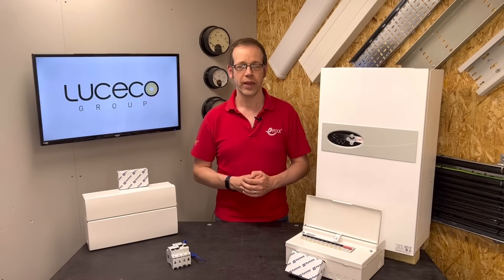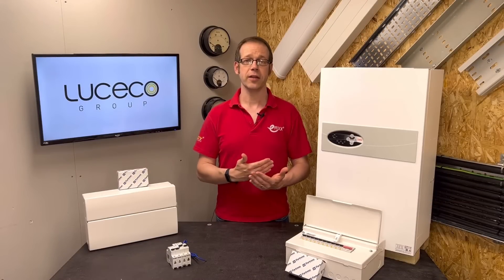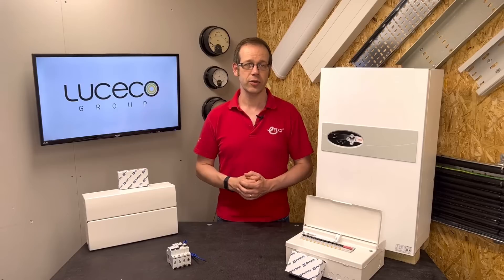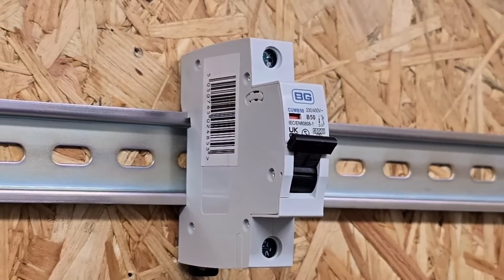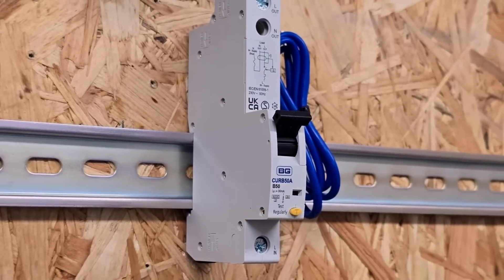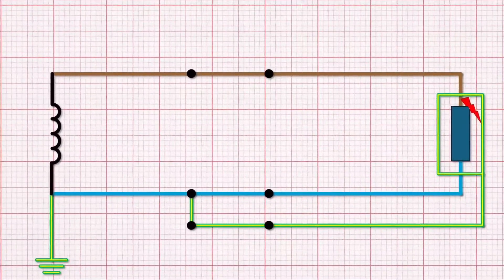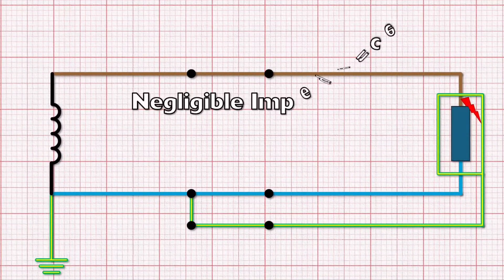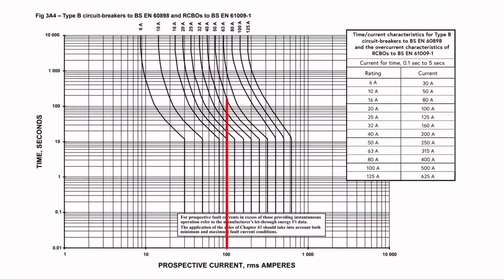If you remember from part one of this training module, we stated that this cable would be surface mounted or clipped direct along its entire length and isn't buried in a wall, so it doesn't require RCD protection. This was a very deliberate choice so that I could explain clearly how to do simple circuit design and demonstrate the use of MCB protection - because if we do use an RCD for additional protection, it can change some of our values. So let's toy with the design and say it does need an RCD. What's the impact?